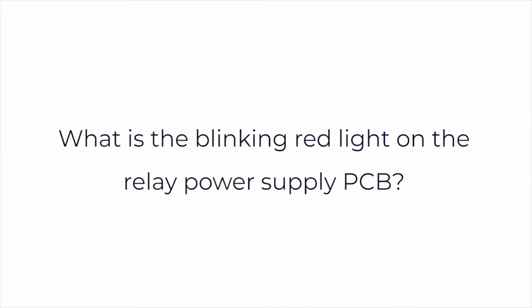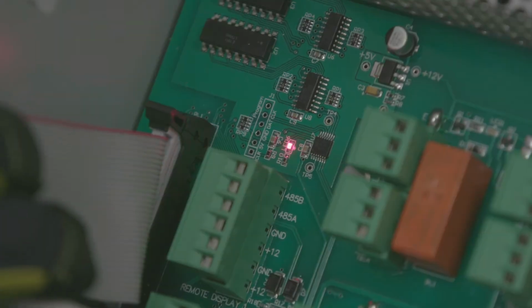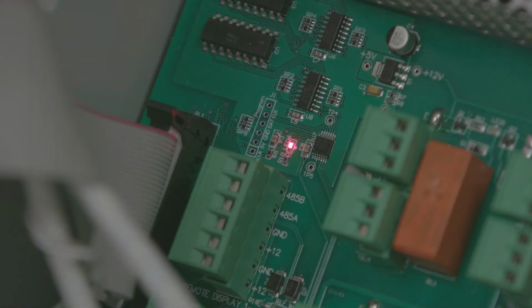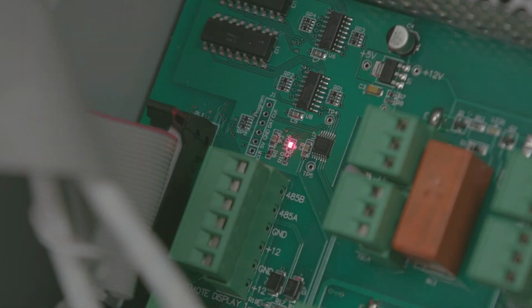What is the blinking red light on the relay power supply PCB? That indicates the communication status of the RS-485 signal between the control unit and the remote display. Blinking once per second indicates all good. If the red LED on the relay power supply PCB is blinking every 5 seconds, it means that there is no transmission of signal.